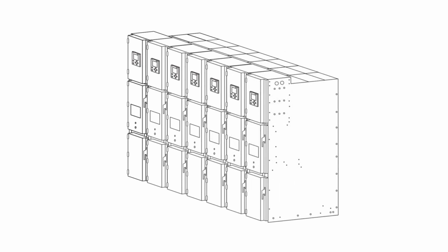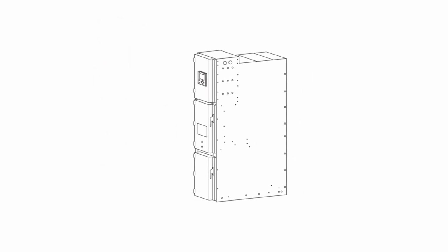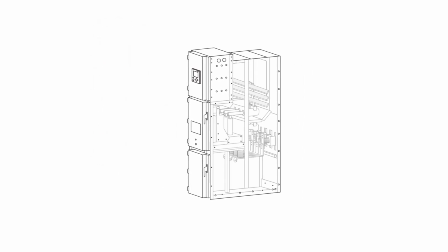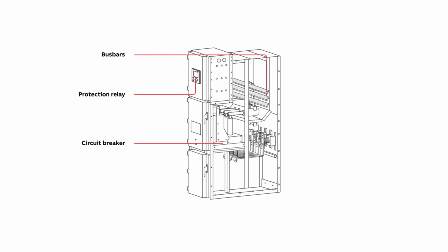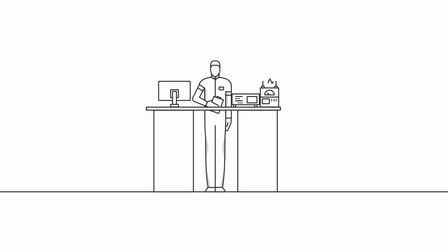In our example, we're using ABB's Unigear switchgear. The switchgear consists of 3 typical bays. The switchgear has truck-mounted circuit breakers and protection relays. There are also arc sensors installed in different parts of the switchgear to detect arc flash. Now, let's meet Matthew. He works as a protection engineer, and he is creating a protection scheme for the Unigear.